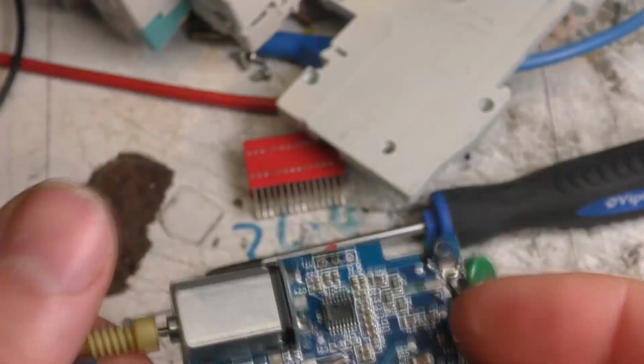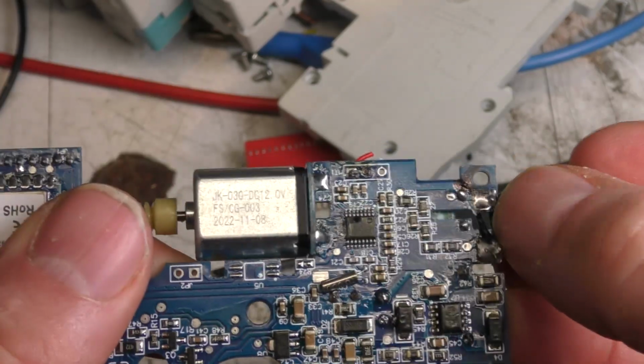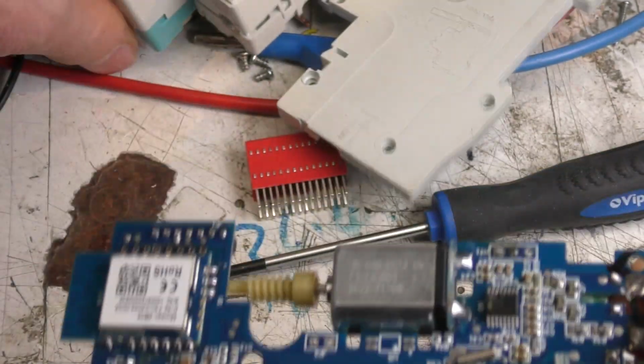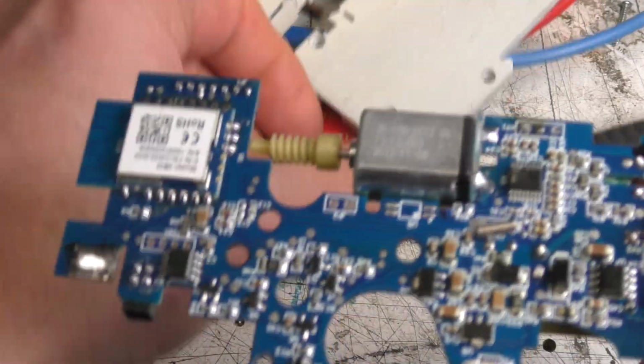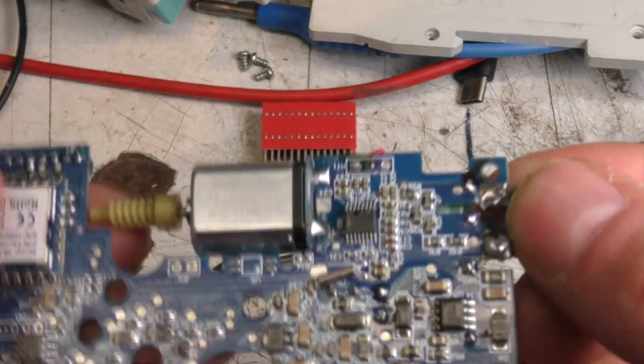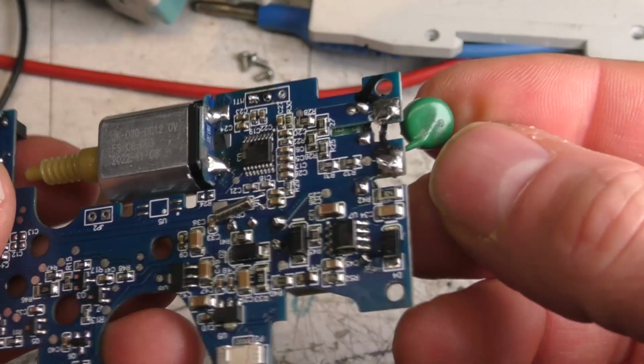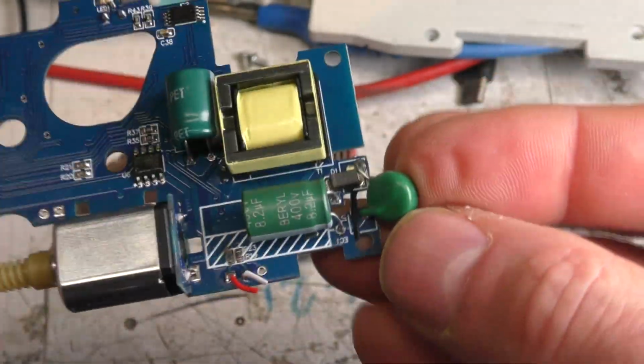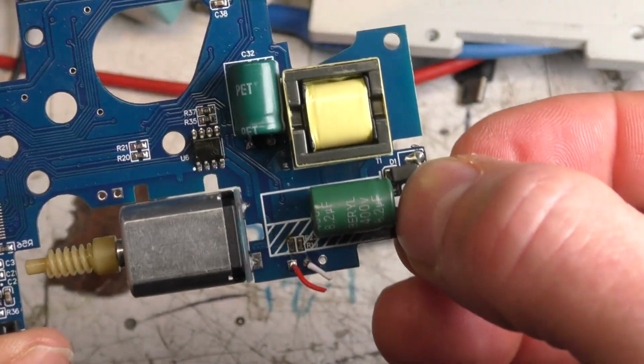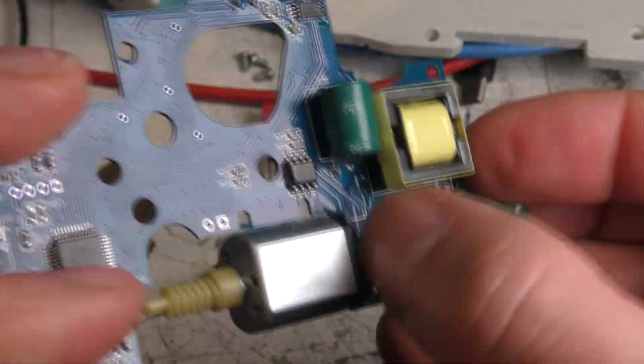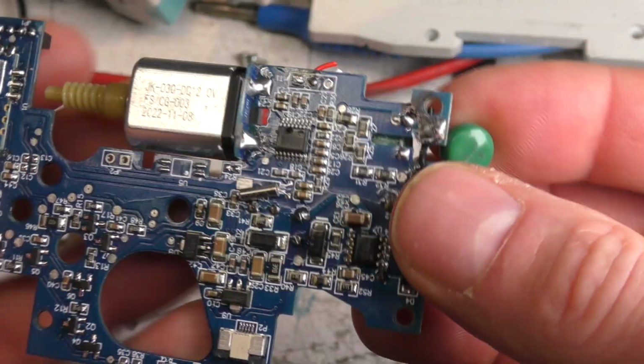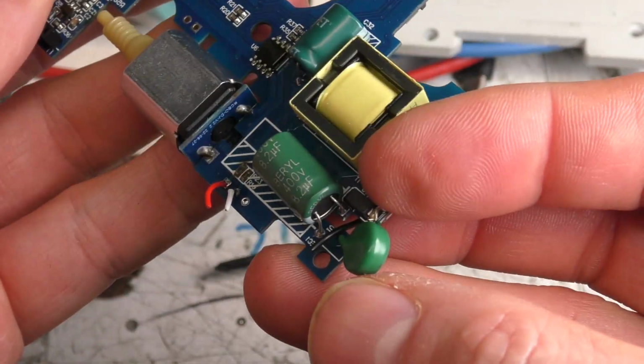What is a bit of a concern is that you've got the mains feed coming into the board here, and there appears to be no fusing at all. Obviously, if this is part of a distribution system, it could be connected to a supply cable of maybe 100 amps or something. Yeah, it goes straight into this MOV with no fusing, through this diode into this capacitor. So if those failed short, then this whole thing could make quite a substantial pop and cause a fire.